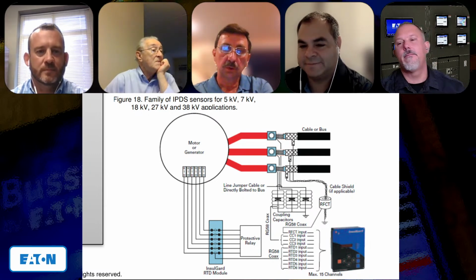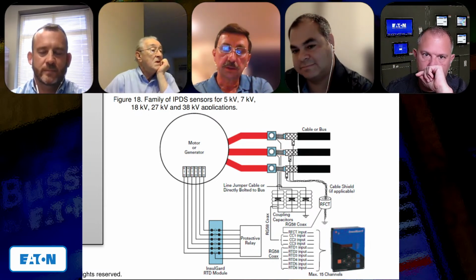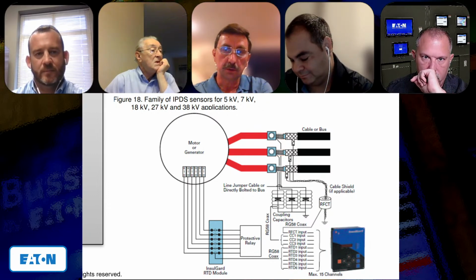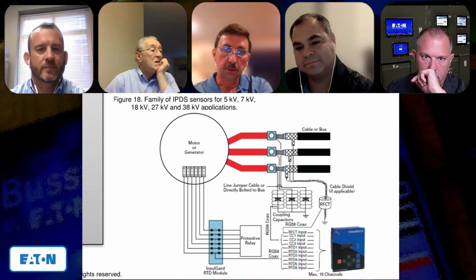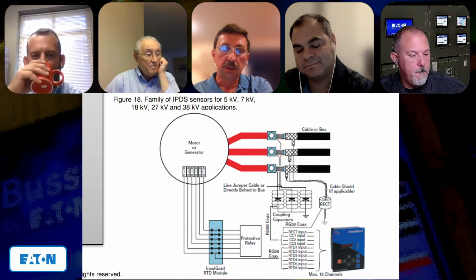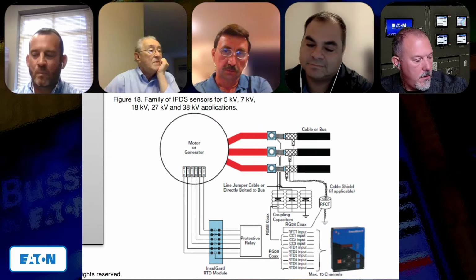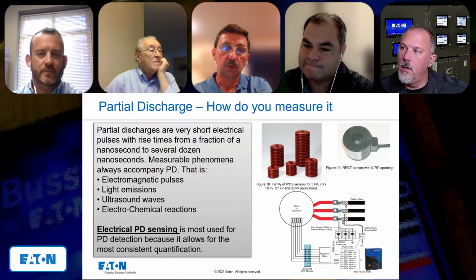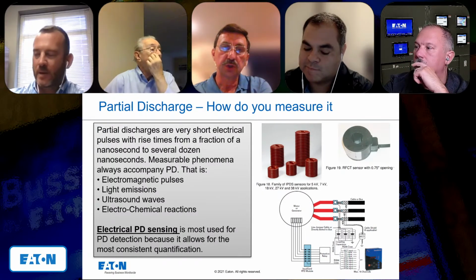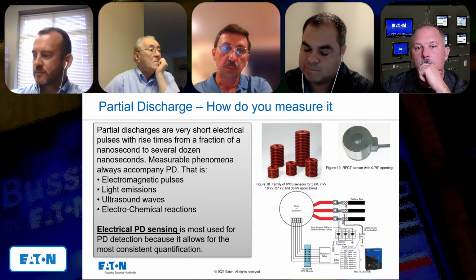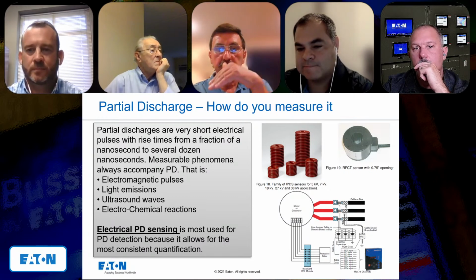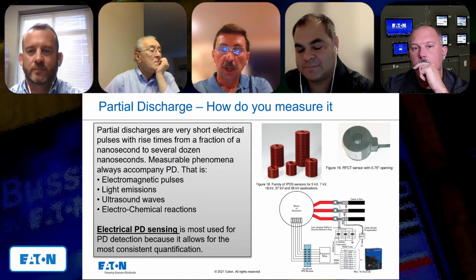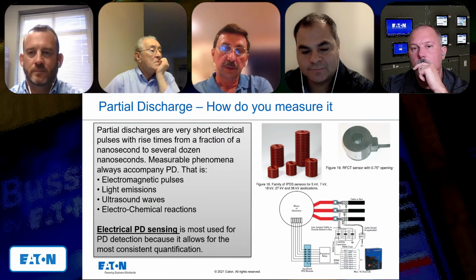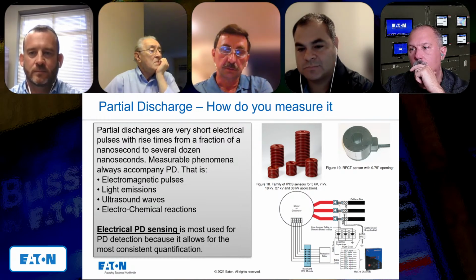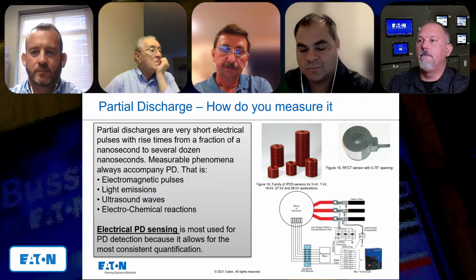Correct. The value of InsulGard is that it provides long-term monitoring and recording of data, and what should cause the most worry for the end user is a quick change in trends. That's the time when you have to take a look at the device. If something is changing quickly, in both directions, decreasing the partial discharge activity or increasing it, both could have a reason of insulation degradation. So that's what it is.